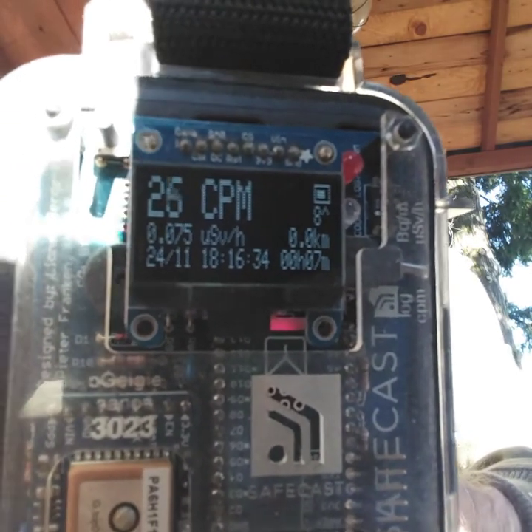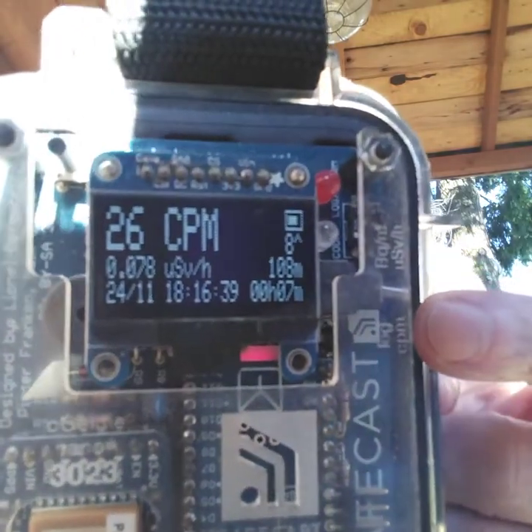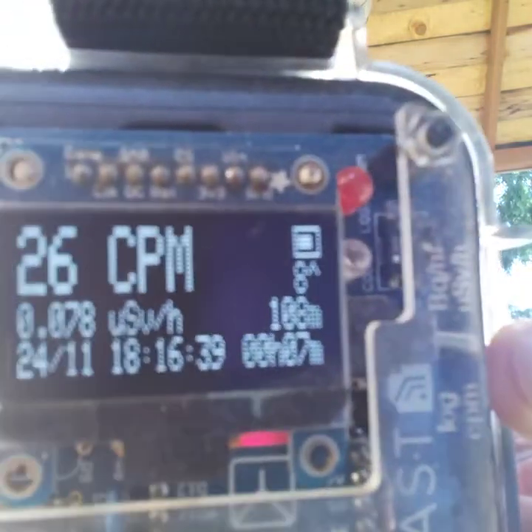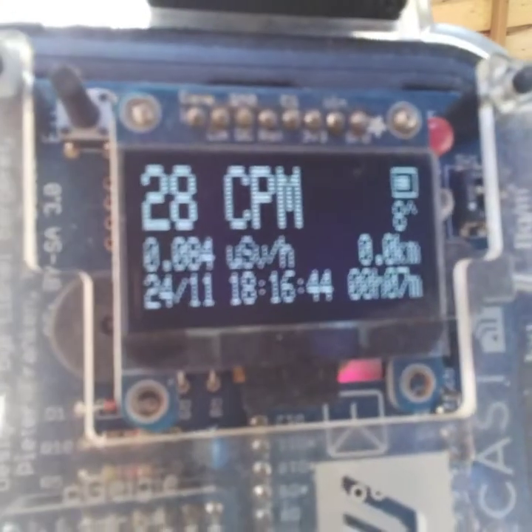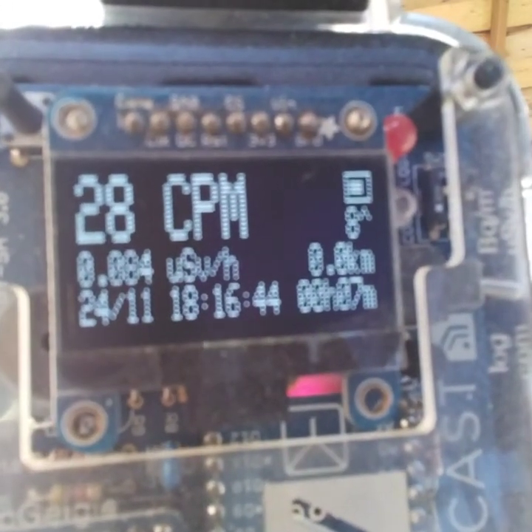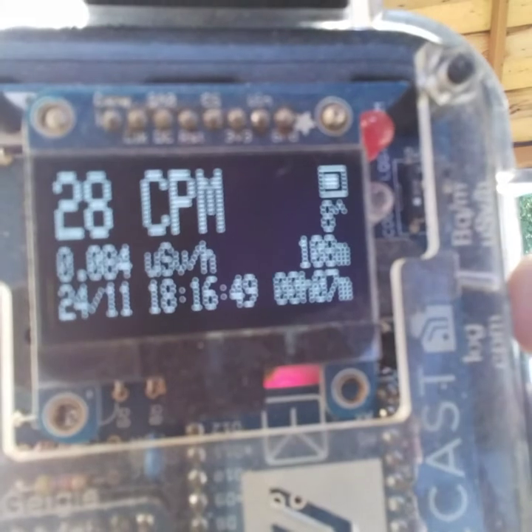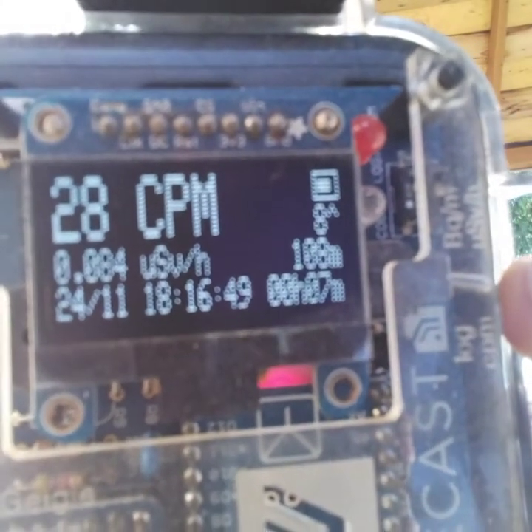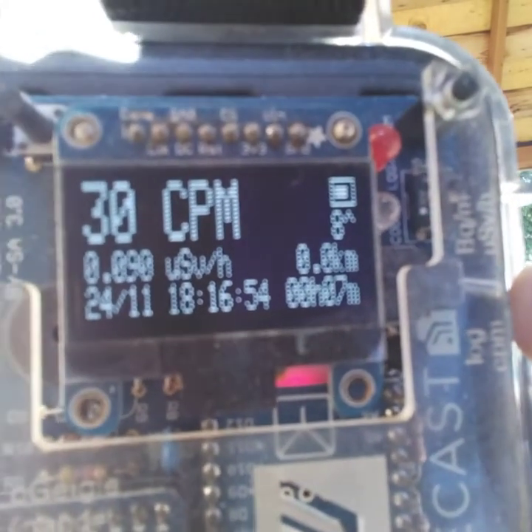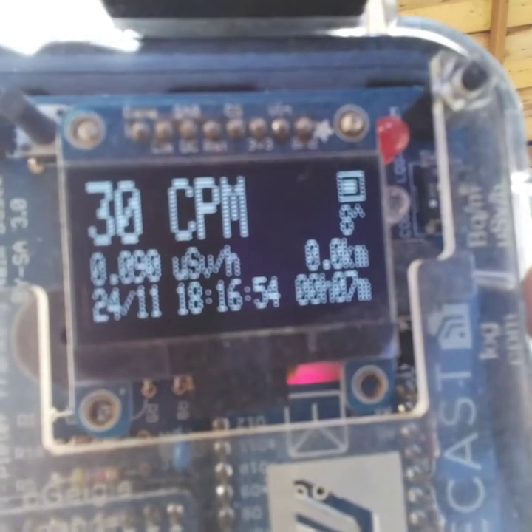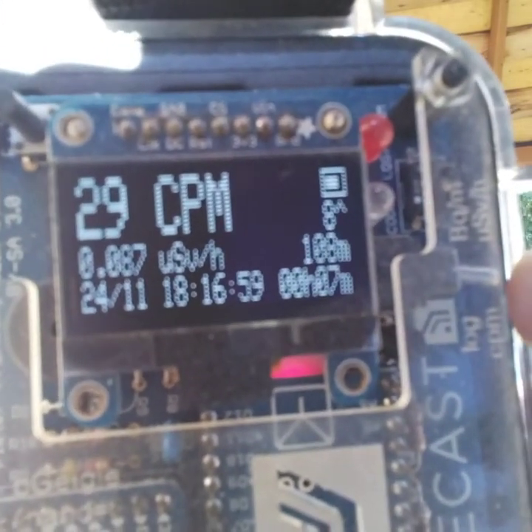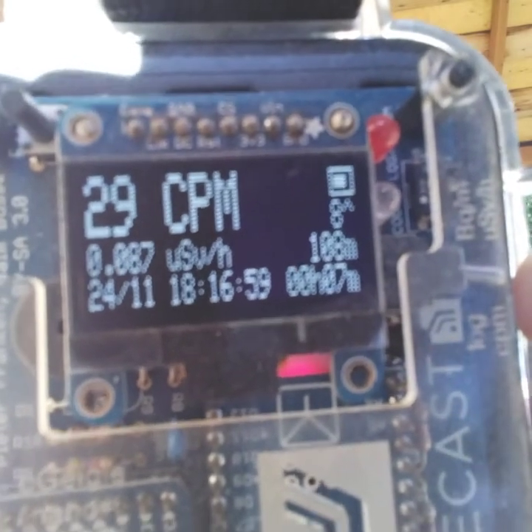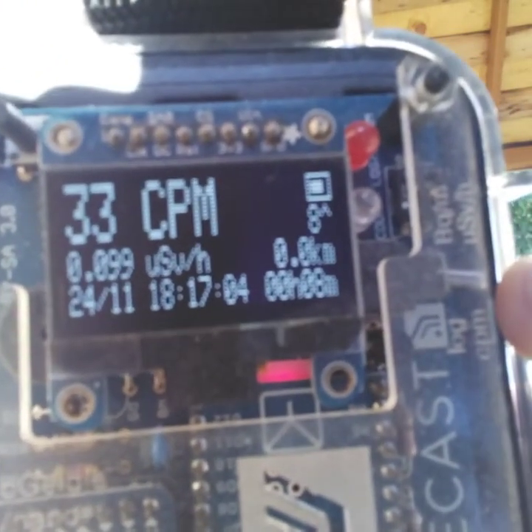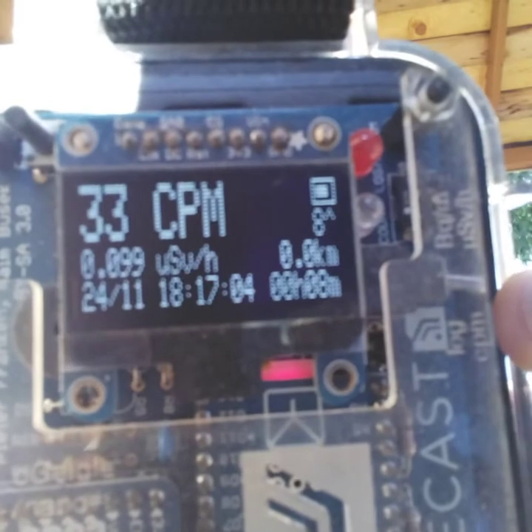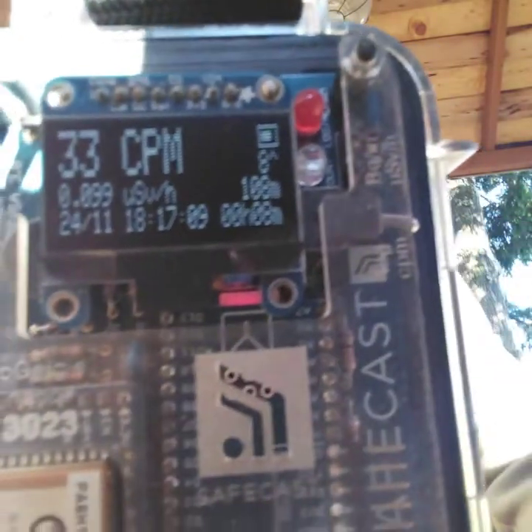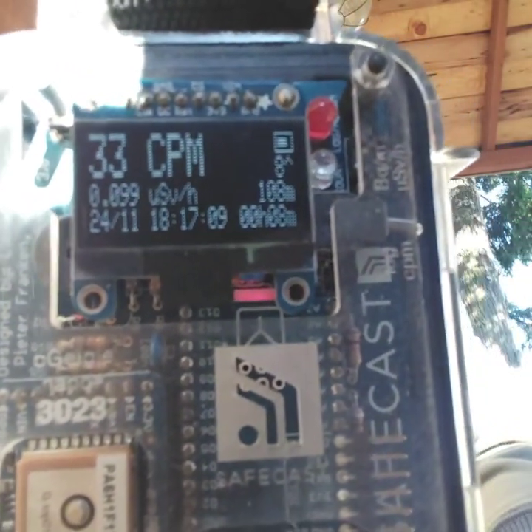The counts are what it's actually seeing, and that measurement in microsieverts per hour is a derived number based upon this tube's characteristics. There's one number you enter in there that is a multiplier for what the counts coming off the detector are. Could be considered interesting stuff.